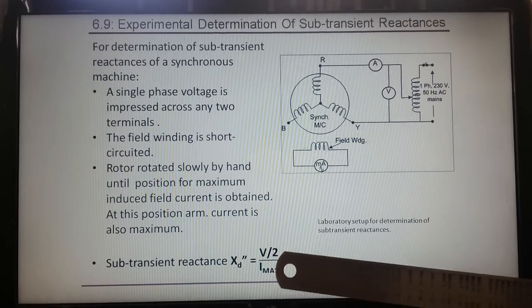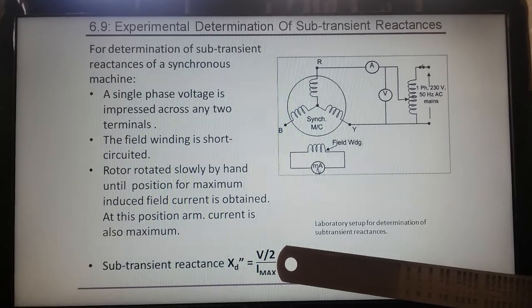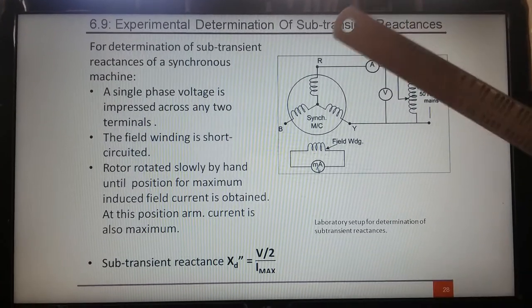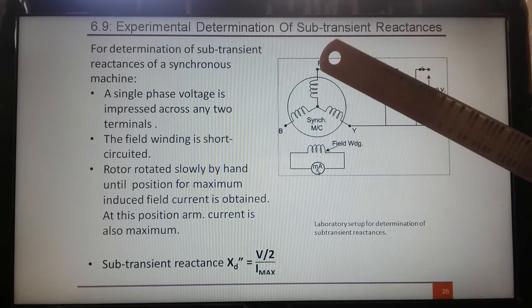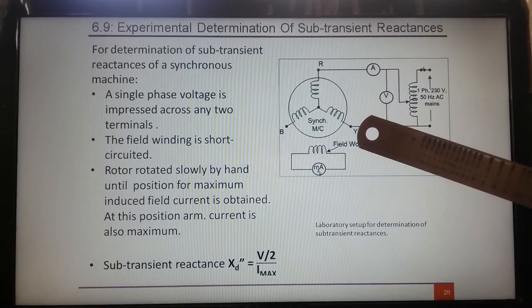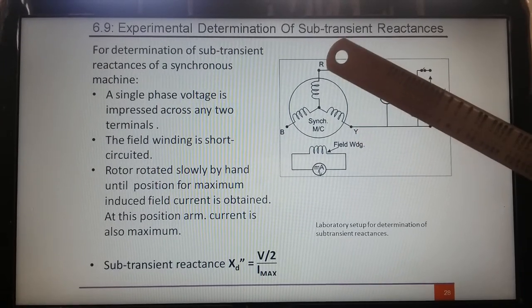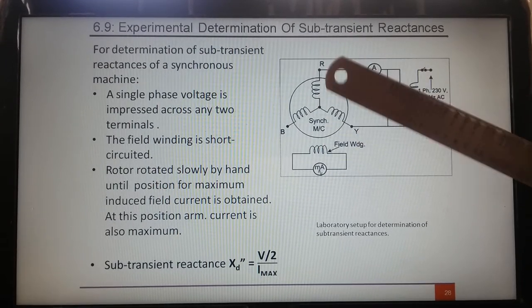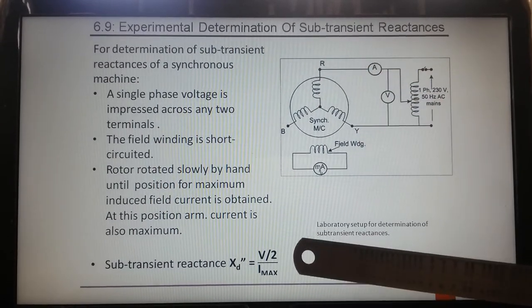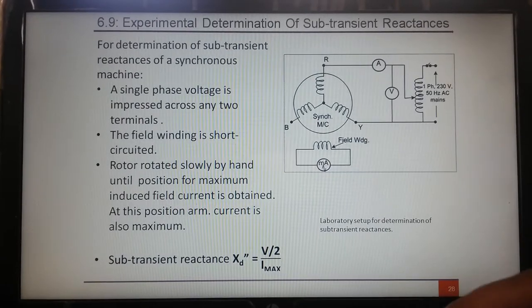The maximum current is recorded, and the voltage in the numerator is V by 2, because the voltage is impressed across two terminals, so for one phase you need to divide by 2. That gives XD double dash.